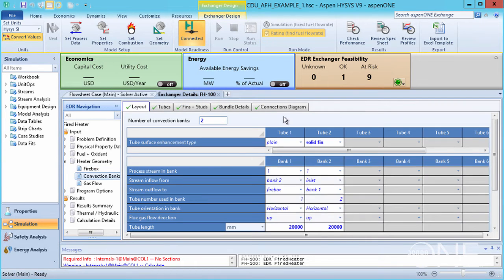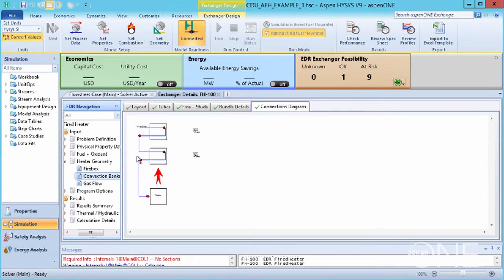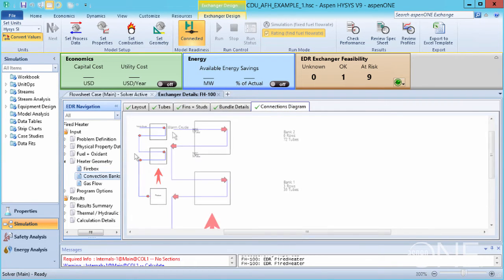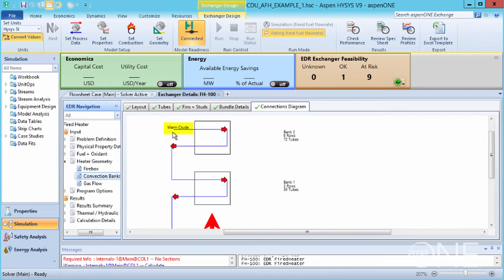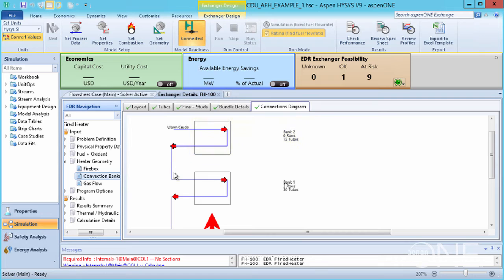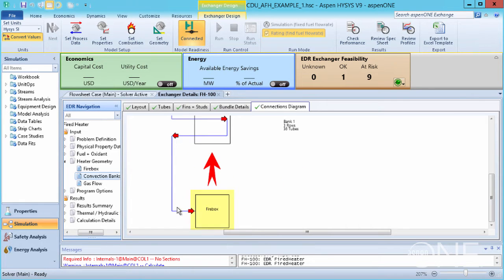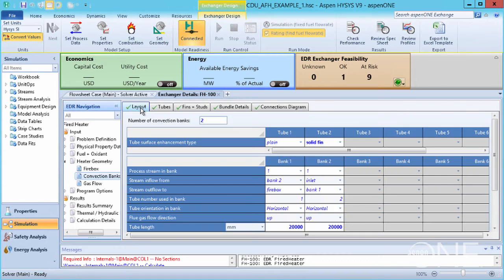Starting with the connections diagram. This shows us how the process stream, the warm crude, flows through the heater. It enters the second convection bank, flows through the first convection bank, then goes through the tubes of the firebox. If we go to the Layout tab, we can see how the program has defined the flow of the process stream through the heater. Bank 2 is the default inlet, and the process stream flows from bank 2 into bank 1.